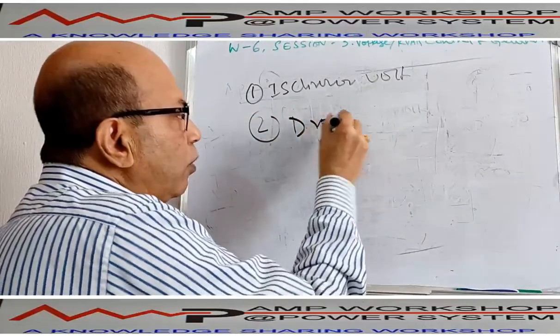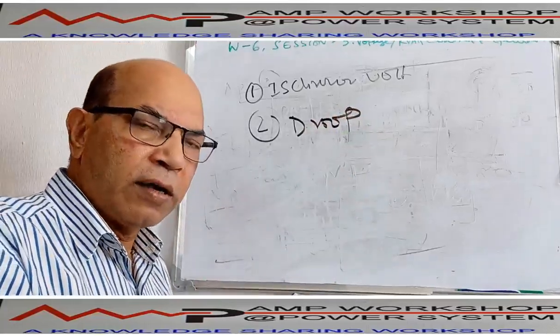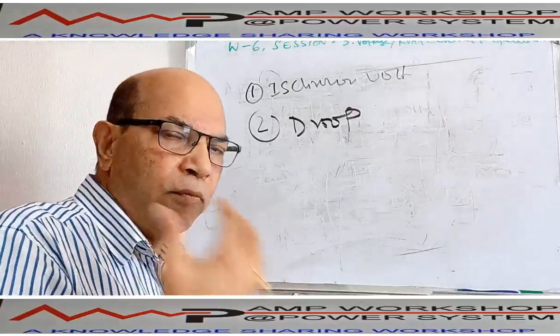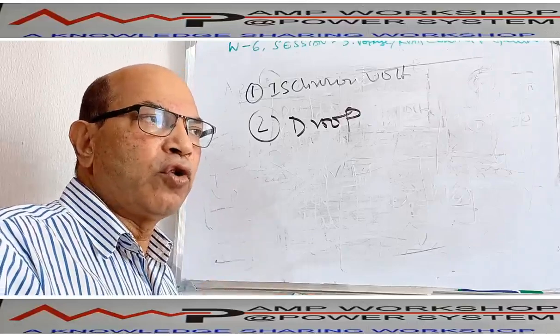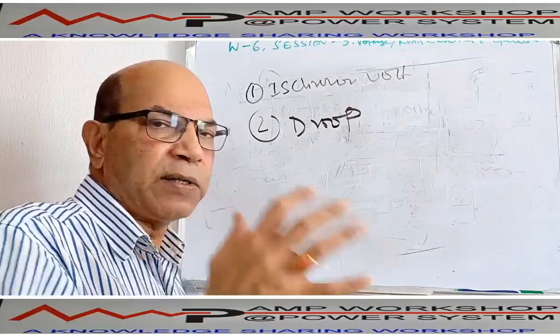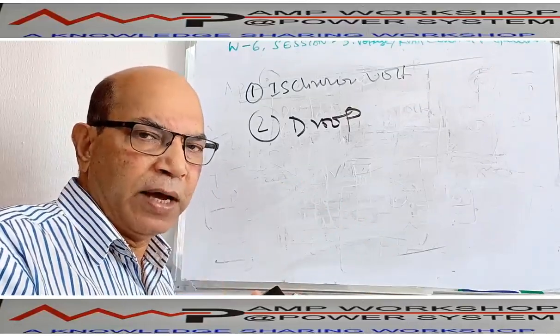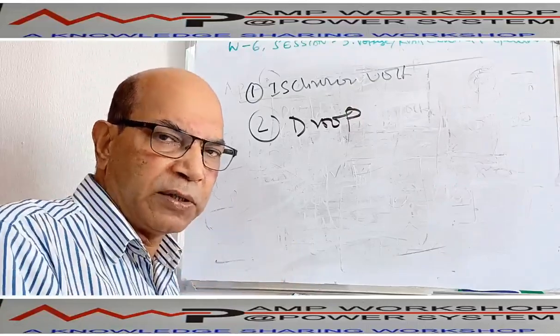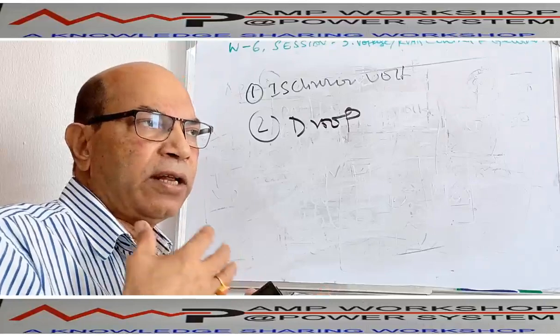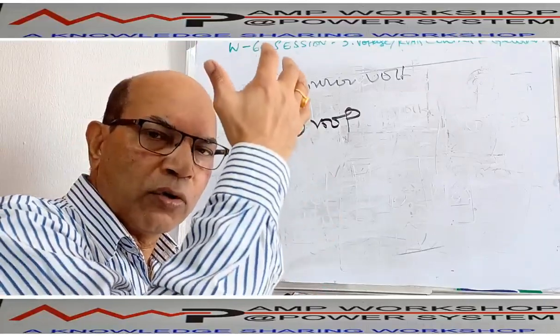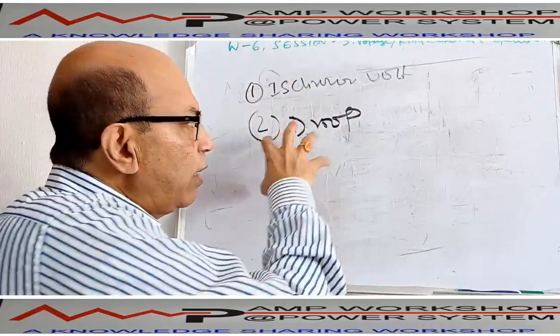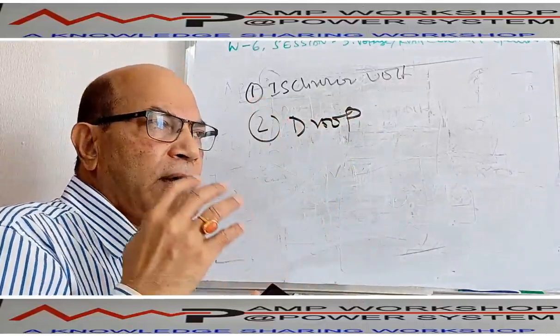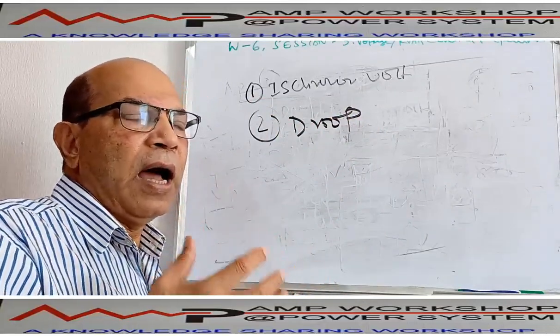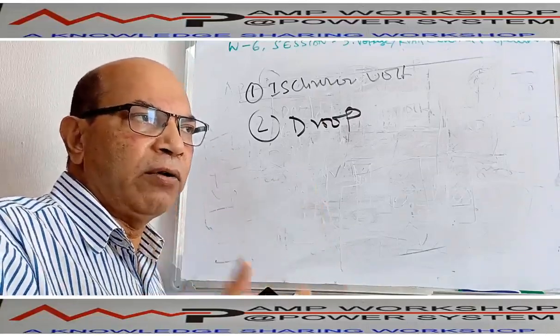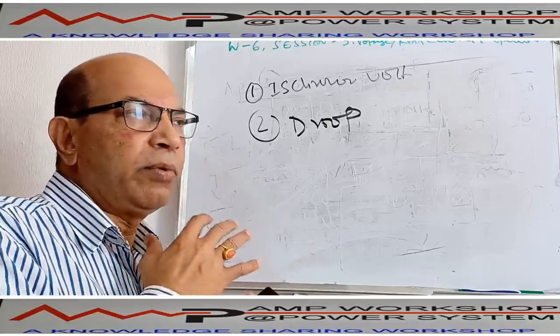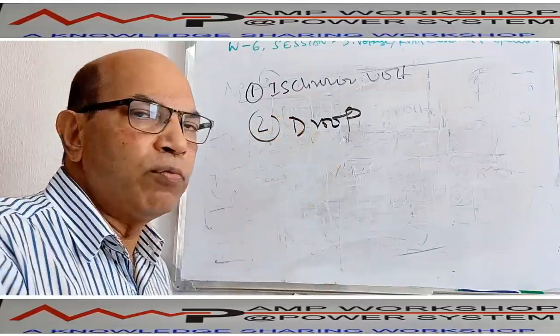Another we call droop voltage mode. In that case, what is happening? As you draw more and more reactive power from the machine, voltage will drop more and more. Suppose the machine is loaded at 100% of its KVAR capacity, the rated capacity. If you load the machine 100%, then it will come to the rated voltage. But when there is no KVAR load, it will go to its no-load voltage, that is the maximum voltage. So droop mode is a mode where the voltage depends on how much KVAR load you are putting on the machine. If you increase the KVAR load, voltage will drop and drop. At 100% load, it will be running on the rated voltage. That we call droop mode. These are the two modes.